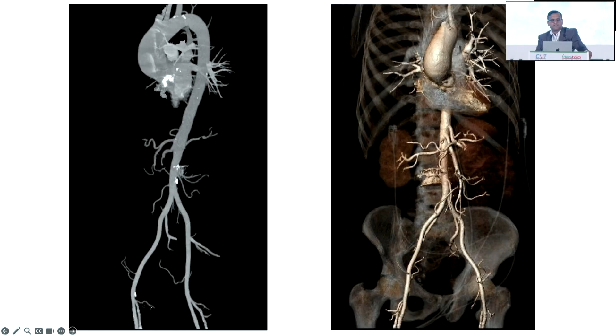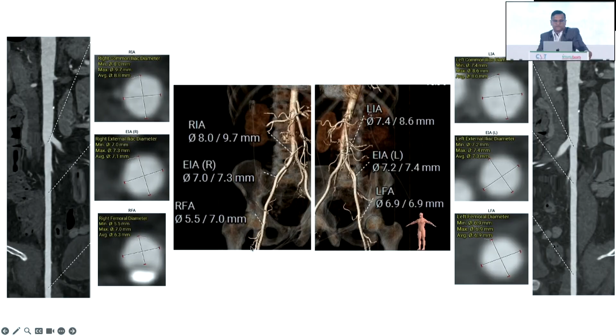The second thing is you should know the diameter of the artery and the diameter of the device that you are going to use. If the ratio is more than 1.1, then you should keep in mind that you have a large chance that it is going to perforate or something like that. And you should be very careful about that. You should scan the whole segment for the size of the artery and not rely on a single place measurement.